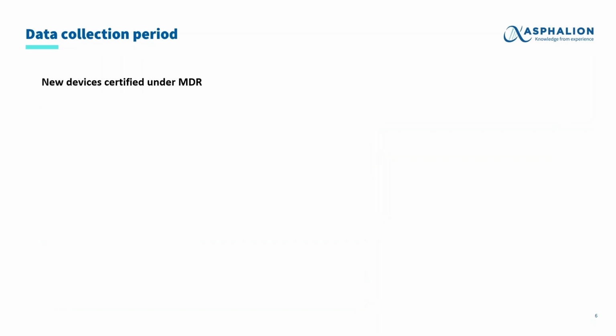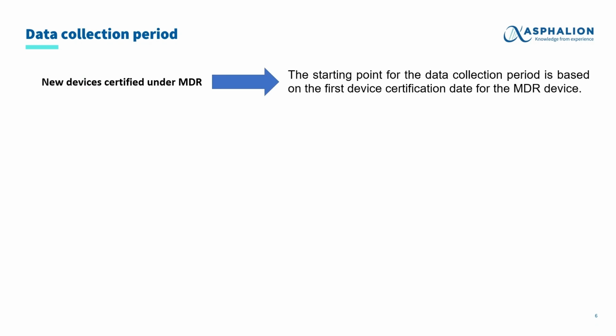Then, when does the data collection period start for a PSUR? There are different possibilities according to the certification of the devices. For example, for new devices that are only certified under MDR, the starting point for the data collection period is based on the date of certification.